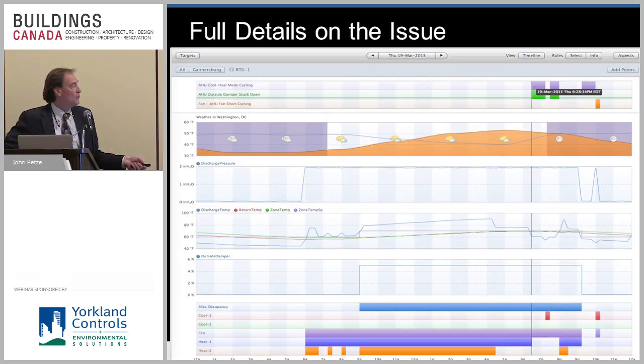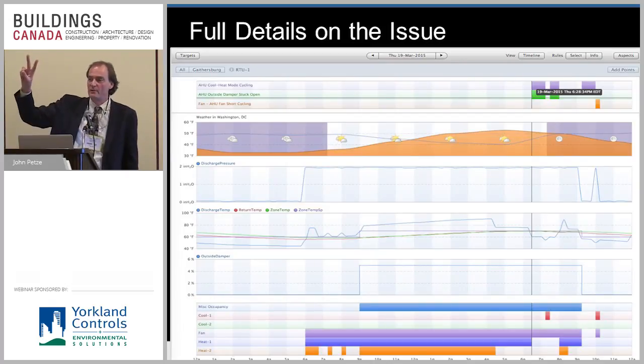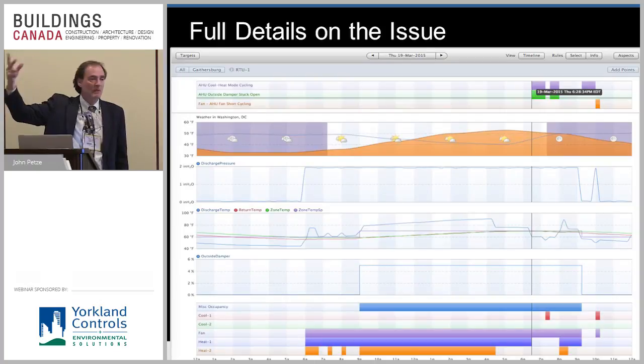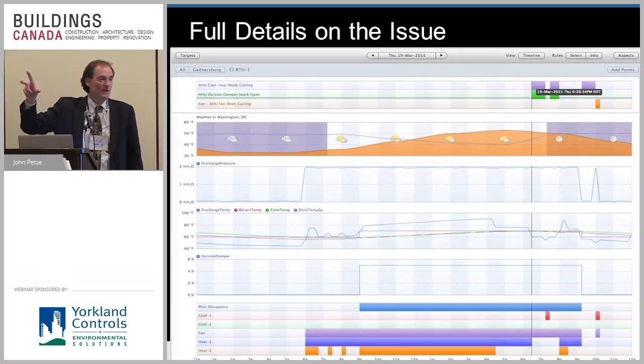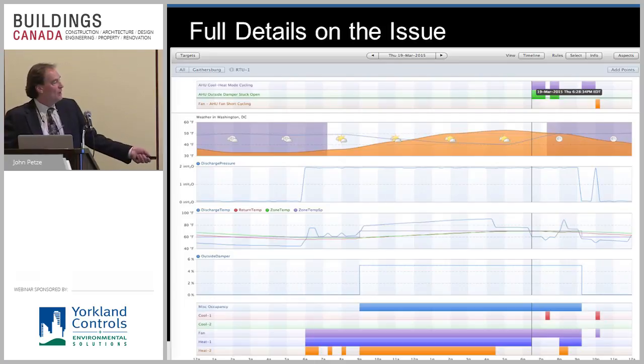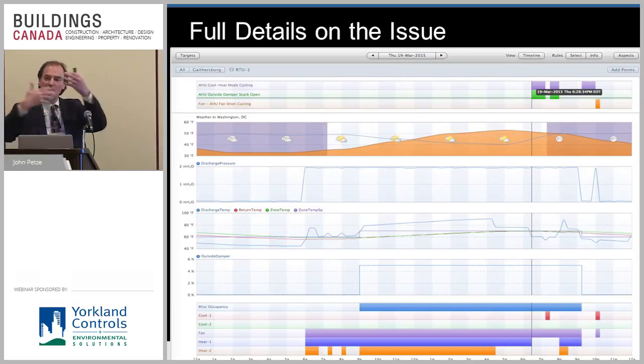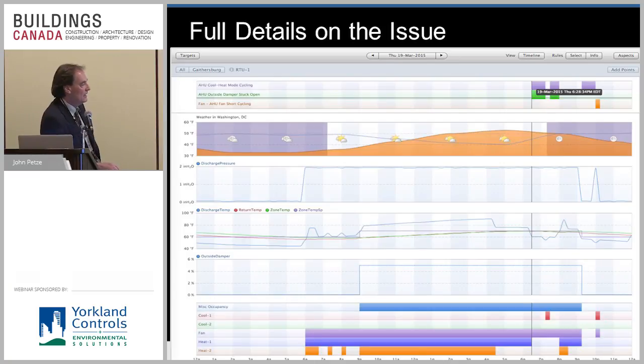I should get the outside air damper control signal, because I'm supposed to look at this, and if I look at it, I can show you that's 5% minimum, which is the off position, so I've answered my first two questions. It's not oscillating. It wasn't commanded open. Guess I better get that ladder, right? And down below, it shows us the on-off statuses. And notice it's all aligned. That's one of the key things. All this dissimilar data gets aligned and normalized and correlated. So I can see that my occupancy, this blue line, starts at 9 a.m., goes to 9:15, but my equipment started up at, it happens to be 6 a.m., and the purple line is the fan.